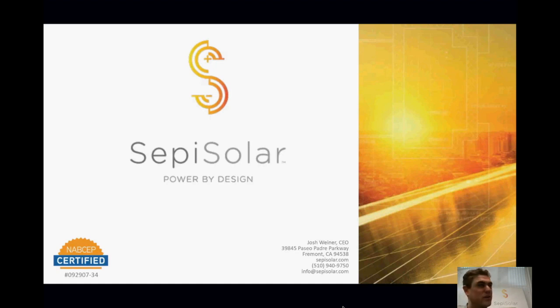You've got a 200 amp service with 200 amps worth of current attached to it—you're done, it's filled up. But because of this 120% rule that Edgar mentioned, you can actually put more energy into that service panel than it's rated for. The logic is that electrons are moving in different directions in that case—there's a difference between sources and loads, so you can think of it differently. This 120% rule has been with us for a very long time in solar.